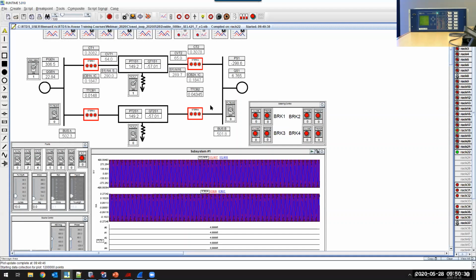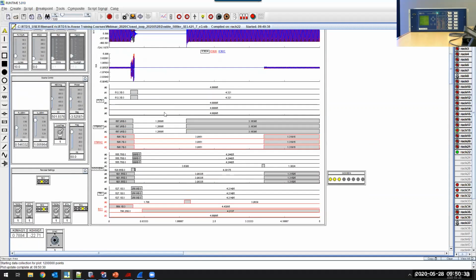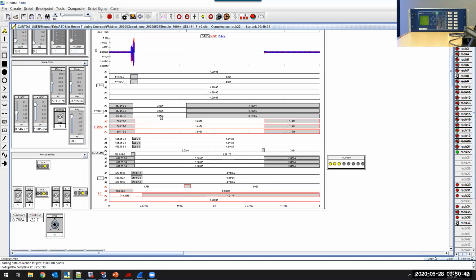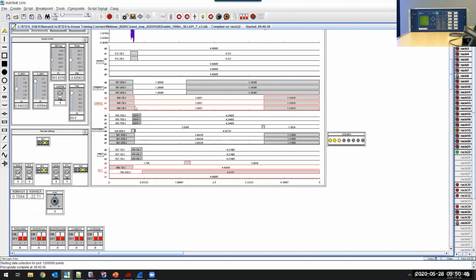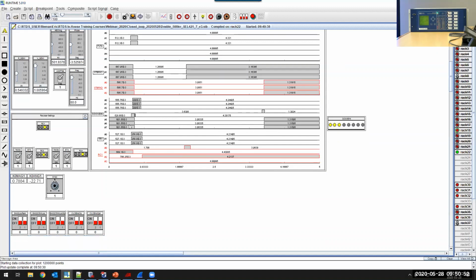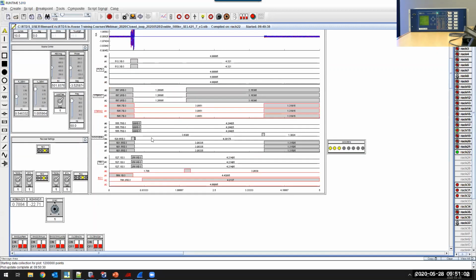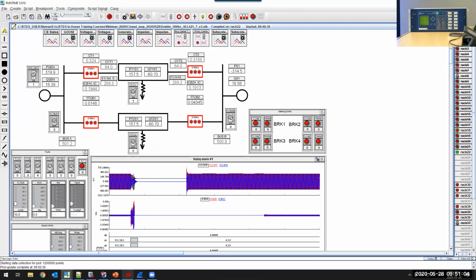Now check out our simulation here. We can see the fault: this is A ground, this is B ground, C ground. So this is an ABC ground fault, right? That's correct. And from the status of the breaker, all 3 phases are opened and then reclosed here. This is the GOOSE input. The relay sent the trip for all 3 phases, A, B, C, and then this is the reclose, and this is the permissive. Let's verify that on the relay side.